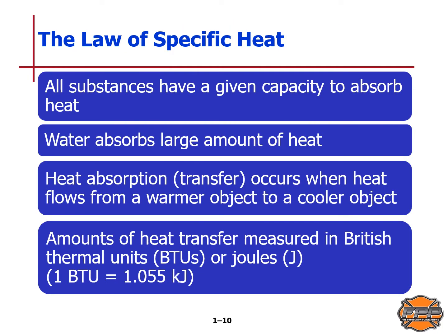The law of specific heat: specific heat describes a substance's capacity to absorb heat. It's expressed as a ratio between any substance's heat-absorbing capacity and that of water. Water can absorb a large amount of heat. Heat transfer occurs when heat flows from a warmer object to a cooler object. Amounts of heat are measured in British thermal units (BTUs) or in joules (J). One BTU equals 1.055 kilojoules. A BTU is the amount of heat required to raise the temperature of one pound of water by one degree Fahrenheit.